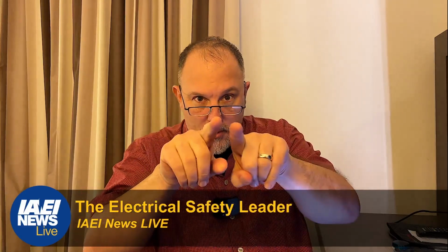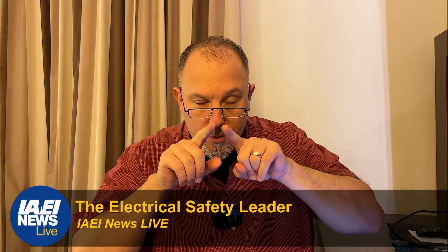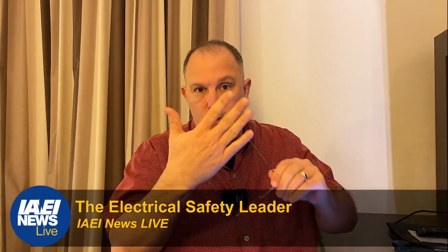So we came up with a technology called a tamper-resistant receptacle. Can't call it tamper proof, call it tamper resistant. And what a tamper-resistant receptacle does is basically you can't put an object into one of those two slots. You have to actually figure out how to simultaneously put pressure on those little doors that are in there to be able to get anything into that receptacle.